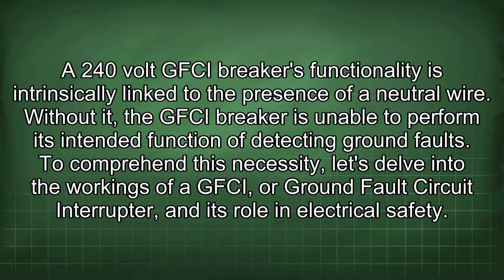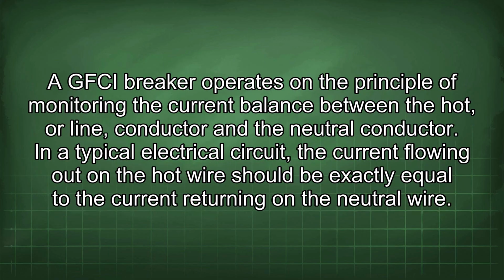A 240-volt GFCI breaker's functionality is intrinsically linked to the presence of a neutral wire. Without it, the GFCI breaker is unable to perform its intended function of detecting ground faults. To comprehend this necessity, let's delve into the workings of a GFCI, or ground fault circuit interrupter, and its role in electrical safety. A GFCI breaker operates on the principle of monitoring the current balance between the hot, or line, conductor and the neutral conductor.